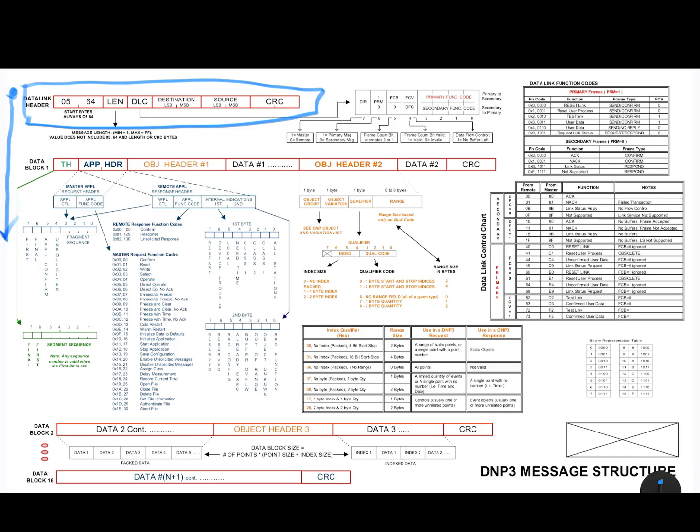It's more like a ping in a network, just verifying that there's a connection and that the outstation is there and there's connectivity between the two devices. So even though there are some messages that are data link header only, and you'd only need to go as far as interpreting that first 10 bytes, there are obviously other messages that do more than that, retrieving object data, binary inputs, analog inputs, and so on.